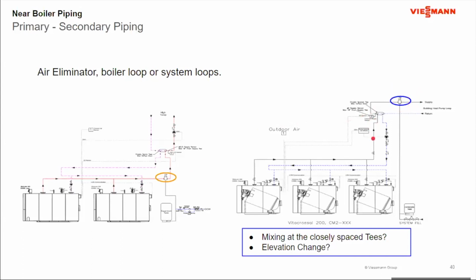Part of the variables are the flow rate in the boiler loop may not match the flow rate in the system loop. So there may be some mixing. That mixing causes the temperature here to go down, which causes the solubility to become less, okay? So it doesn't become a good option. However, all of these are two-dimensional drawings. They don't show 3D. Let's say I had a 3D drawing and all of this was 25 feet off the floor. All the piping was being run across the roof of the building, the ceiling of the building. All of a sudden, with that change in elevation, the pressure changes and the solubility changes as well.